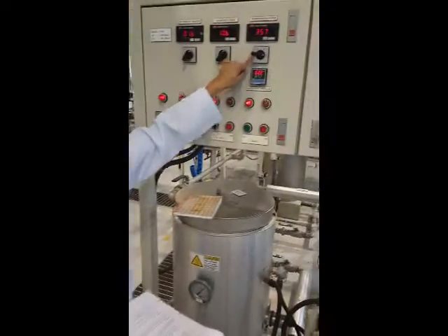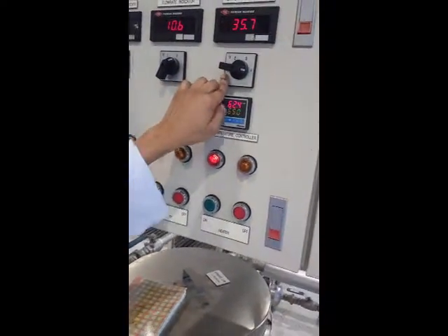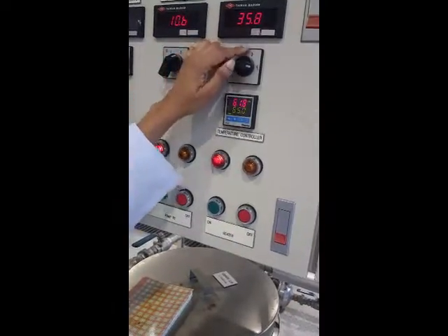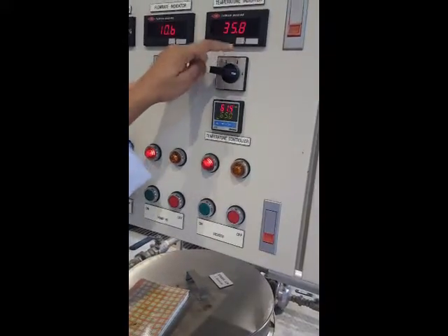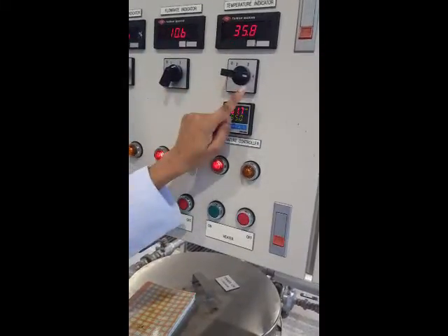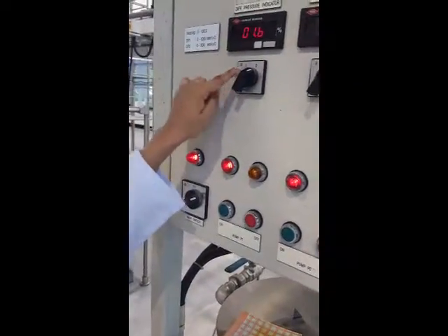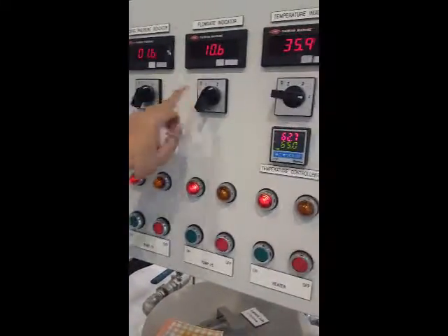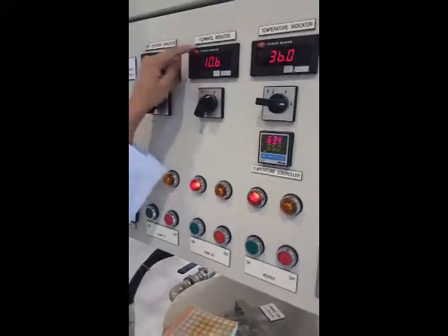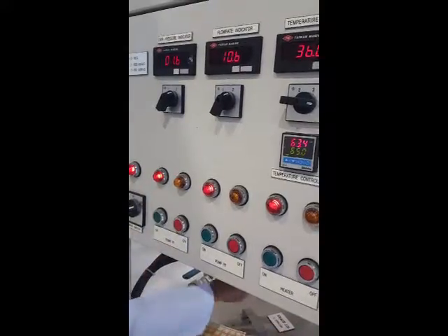For the temperature indicator, when you set it at 1, you record the hot water inlet temperature. When you set it at 2, it's the cold water inlet temperature. As you move on, 3 determines the hot water outlet temperature, and 4 determines the cold water outlet temperature. And this is the differential pressure indicator. You set it as 1 and 2. When you set the hot water flow rate, you have to make sure it's pointing at 2 for the flow rate indicator, which shows that the flow rate is changing.